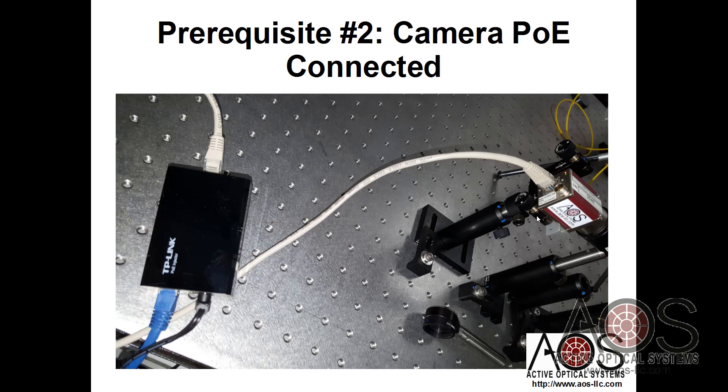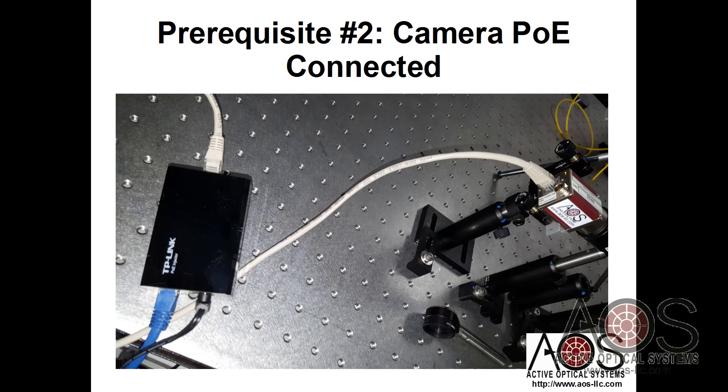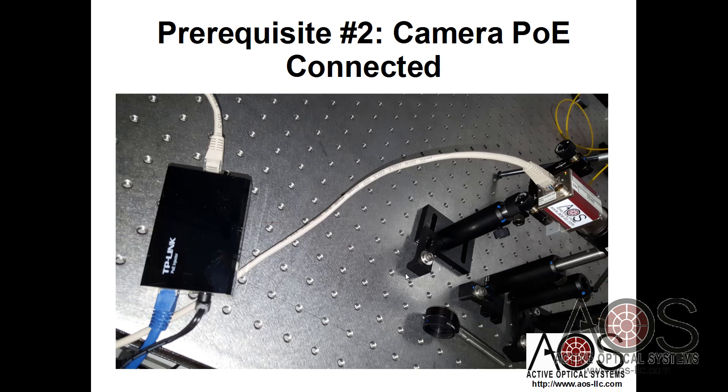The next thing you need to do is plug in all of the hardware. Today we're talking about one of the GigE Wavefront Sensors, specifically one that is Power over Ethernet capable. To use this Wavefront Sensor, you will plug an Ethernet cable into the back of the Wavefront Sensor and into one of the PoE injectors. The PoE injector data line will go directly into the computer or into a switch. We recommend plugging directly into the computer. We find that the connection reliability is better that way.